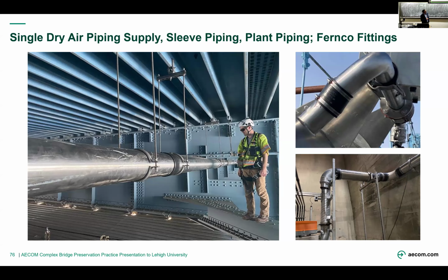Eventually we did make it look better than that. You can see the pipe fitters' work here - this flexible coupler is maxed out in one direction. Originally this was on about a 15-degree slope, and it really should have been welded, because there's more Fernco than stainless steel pipe right here, which in my opinion is the issue.